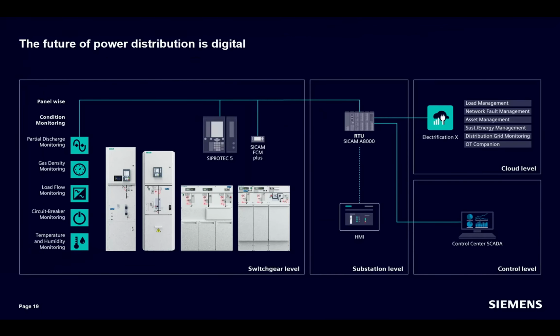Not necessarily. So if we have a look on the architecture of our monitoring solution, we have either in the switchgear or somewhere in the substation level one centralized gateway from our SICAM A8000 RTU family. This RTU collects all the sensor information either directly from the sensors or from intelligent devices like the already mentioned SIPROTEC 5 or SICAM FCM plus devices. This gateway is able to provide a connection to the cloud level or into the control level, or even both levels in parallel are possible. Also, an on-premise solution with an HMI installed in the switchgear or substation level can be realized with the same gateway.